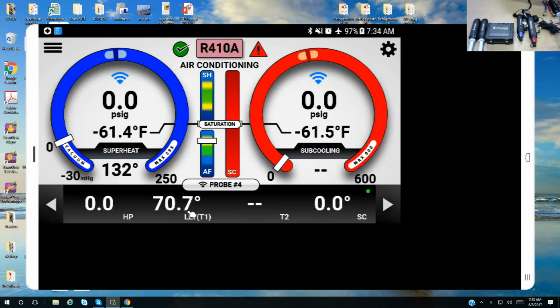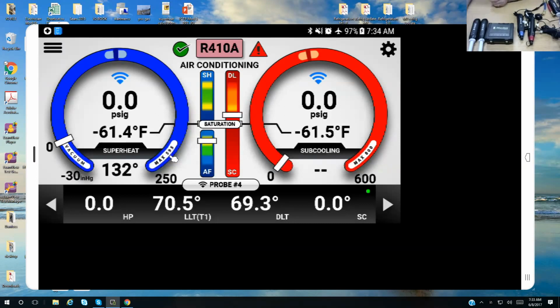If we want, we can plug another thermometer into the side, and we'll map it right from here. I'm going to plug this thermistor into T2. You'll see we get a temperature reading automatically here on T2, and we can map it. Since this is the high pressure probe, let's hook it up to the discharge line. So now we have 4 temperatures reading. On the low pressure probe, we have our suction line and our outdoor air. On the high pressure probe, we have our liquid line and our discharge line. These are the active temps being read right now.